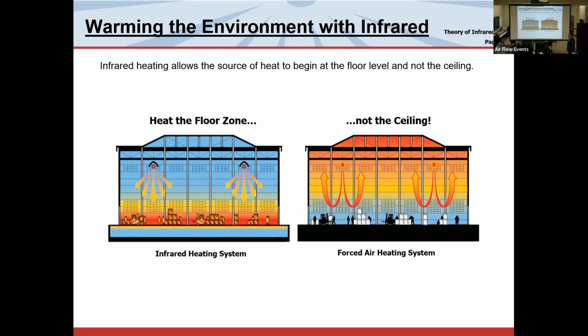And the opposite is when we stick a hot air blower heater high up in the ceiling, heat rises. Okay, if the heat never gets down to the floor, we waste a lot of energy to keep it 100 degrees at the ceiling so that we can keep it 70 degrees comfortable down at the floor. Why not try and keep it comfortable at the floor as your first go-to versus the opposite?